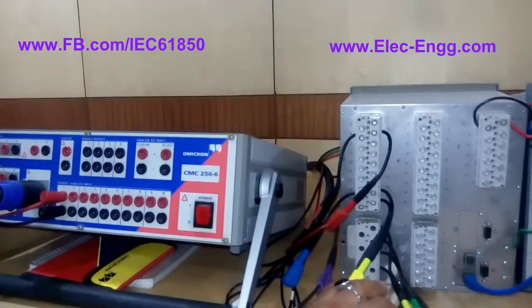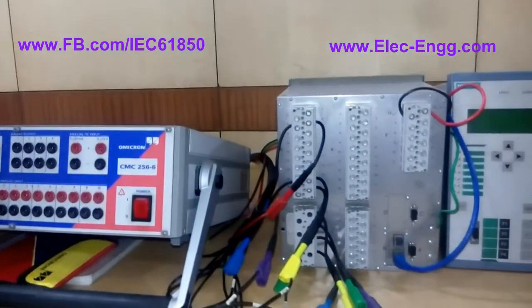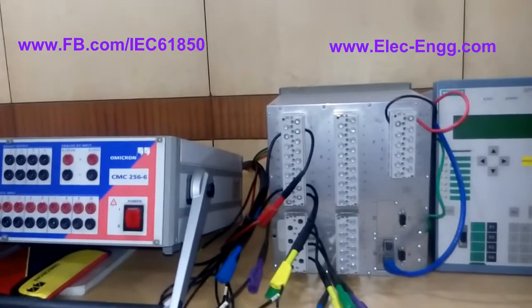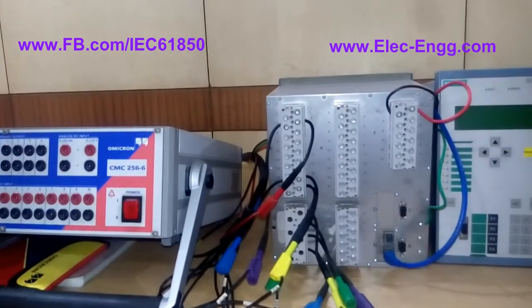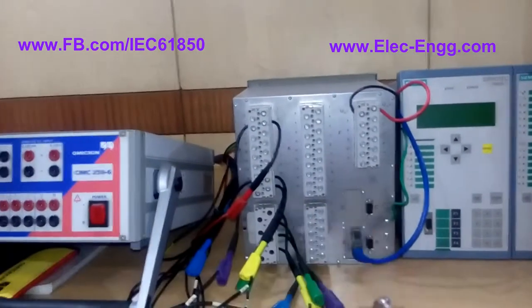This module is an EN100 module which we can connect to the PC and configure through the existing software. We can also connect it to the IEC 61850 network and send signals using that protocol. There are two ports available, as well as serial ports from the rear panel and another serial port from the front panel, also for configuration of the relay.